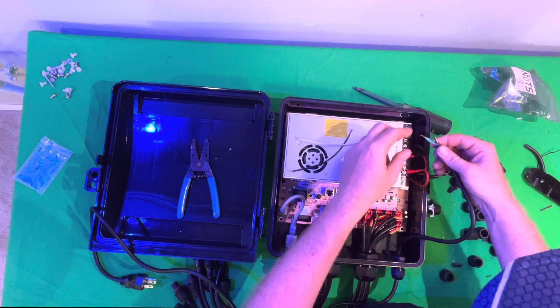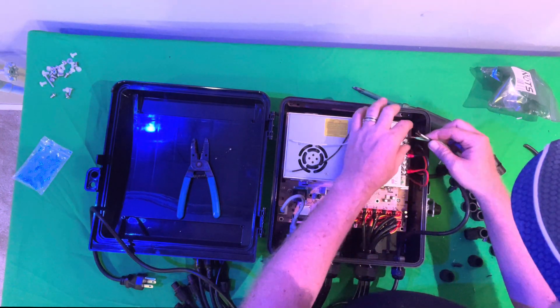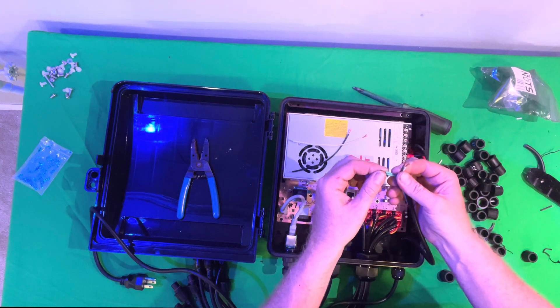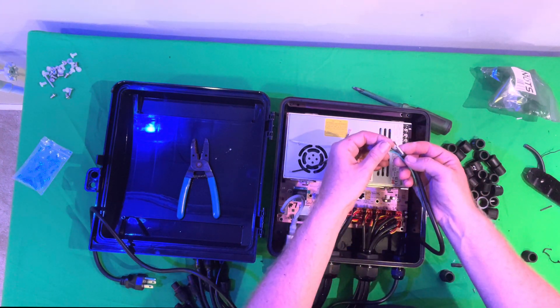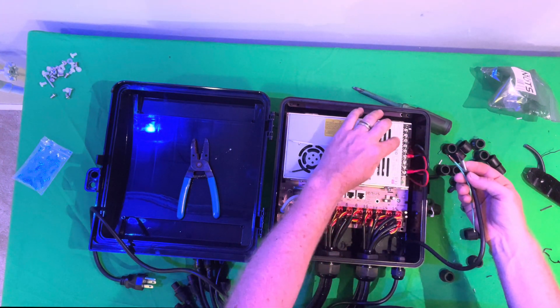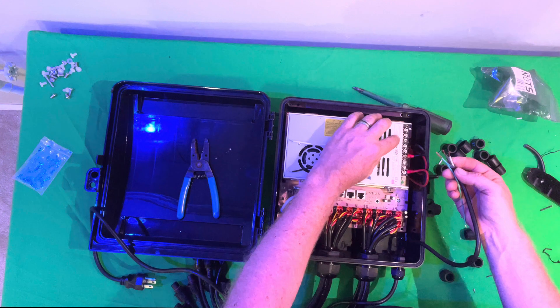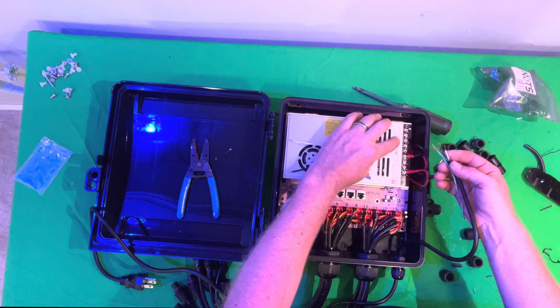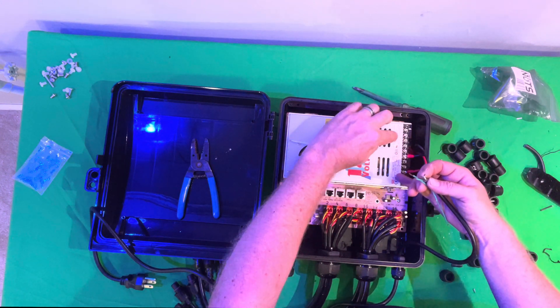In this case, we're just going to do the pigtail. So I'll go ahead and put these in. Green is going to be your ground. White is your neutral and black is your hot or your load. So you're going to do green closest to the DC side, neutral in the middle, and then load furthest away.